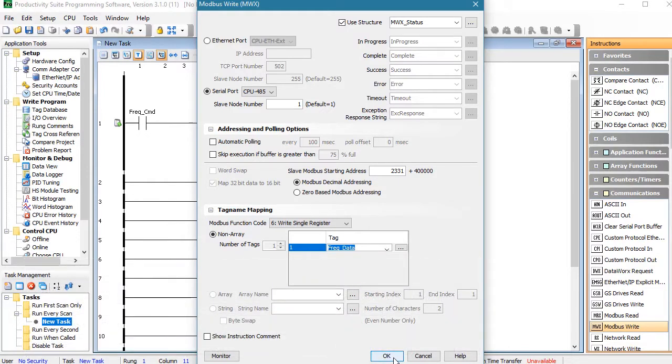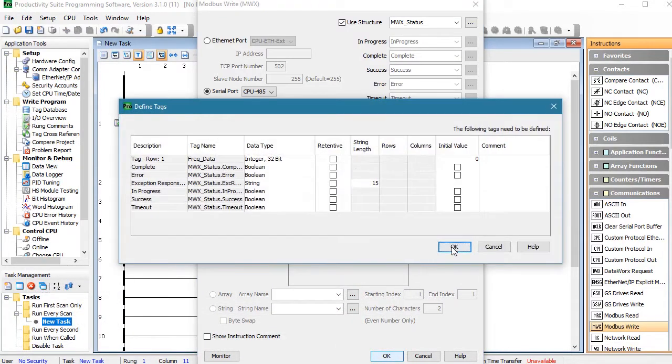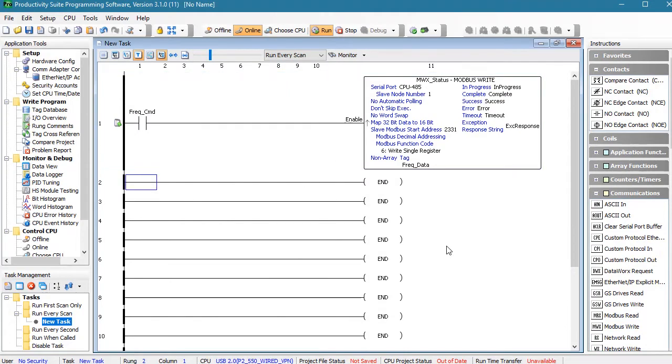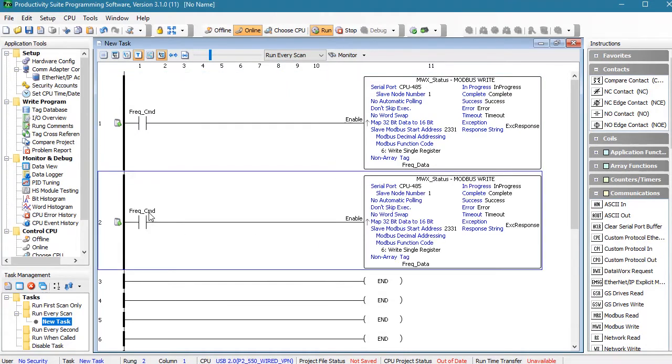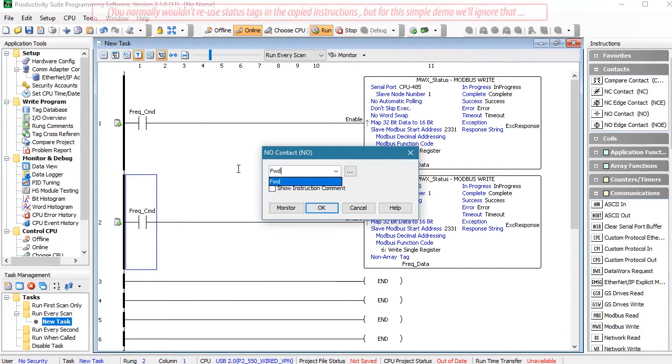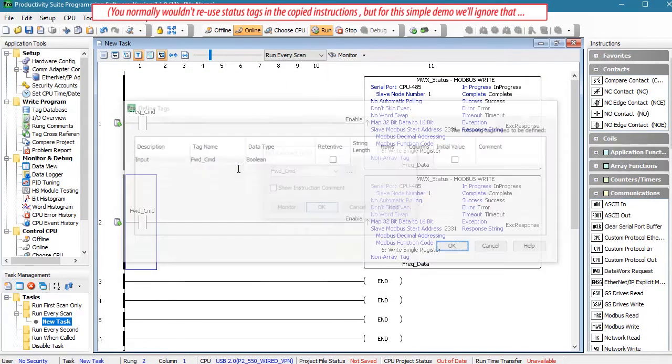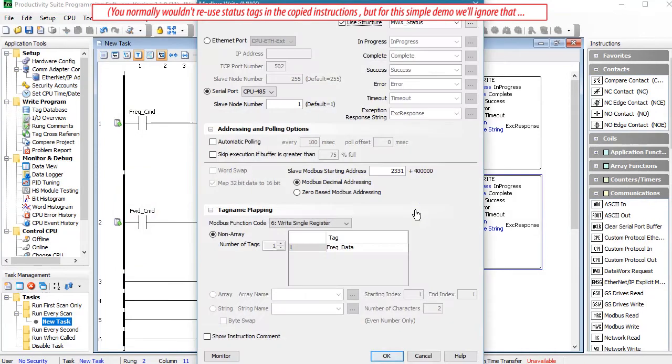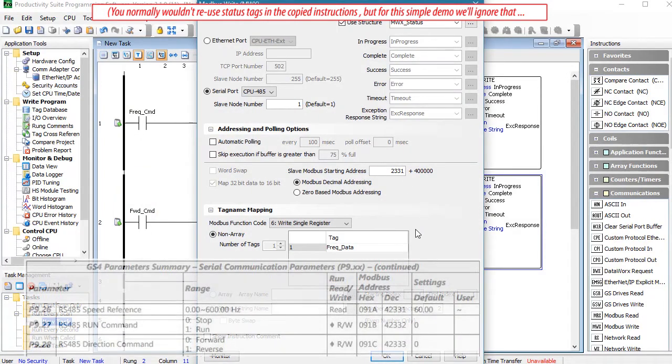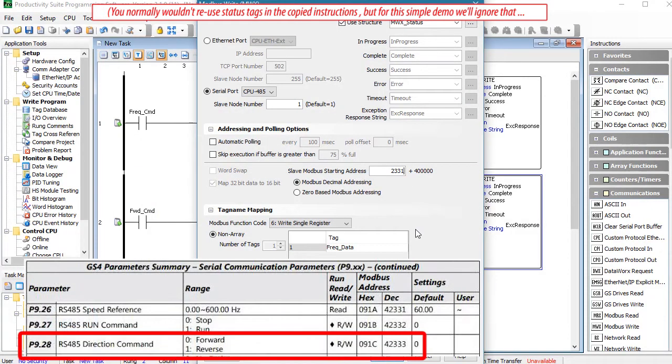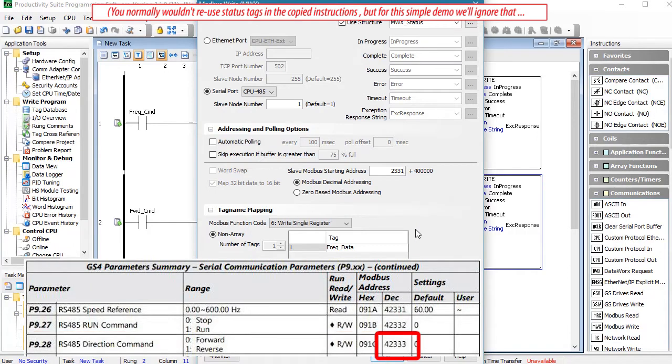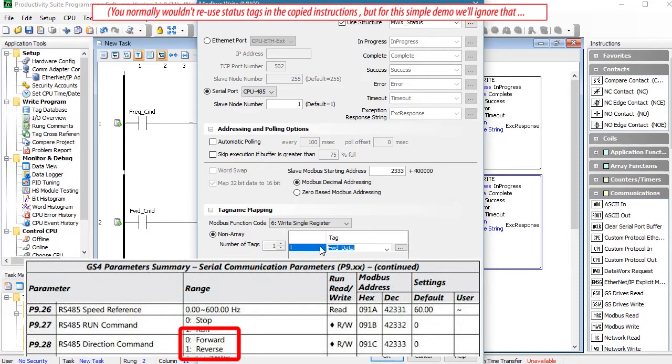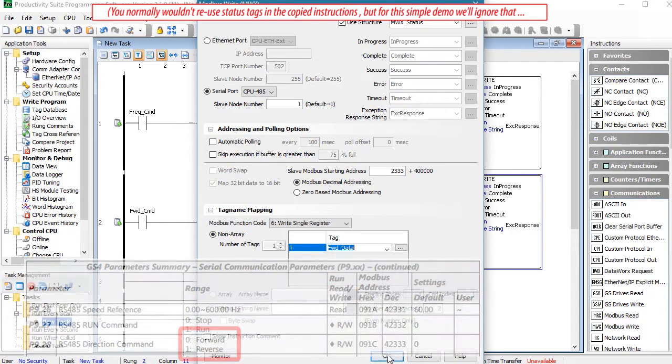Hit OK and these tag definitions look fine. Let's copy that rung and paste it and change it so that a new tag called forward command enables a Modbus write to tell the drive to run in a forward direction. Drive parameter 928 controls that and its Modbus address is 2333, so we put that here. We'll send a tag called forward data. Looks like forward is 0, so we'll set that in a data view too.